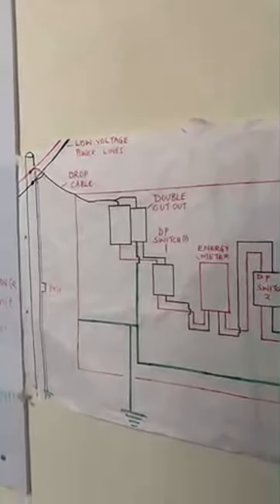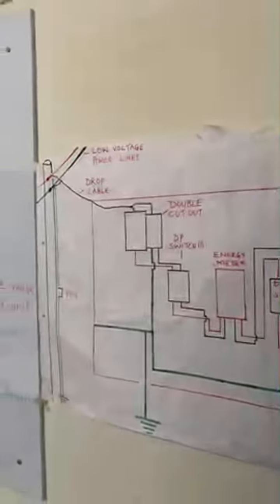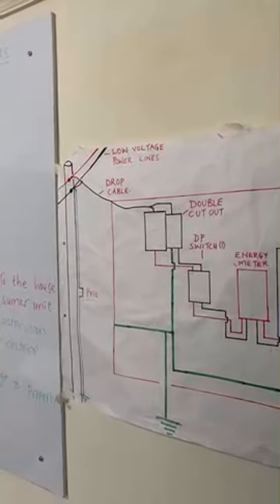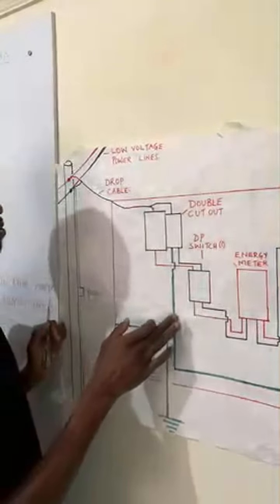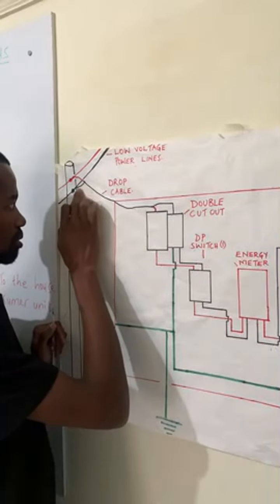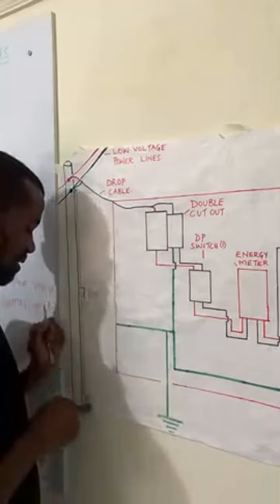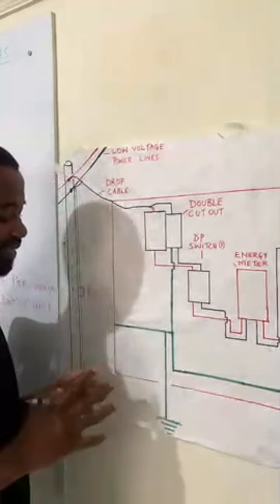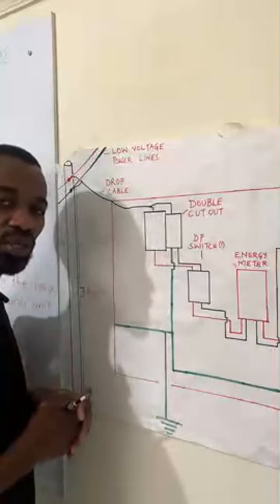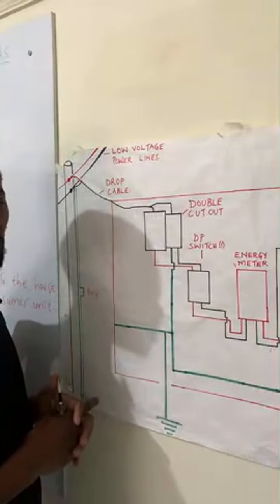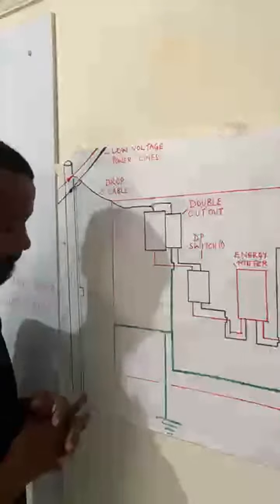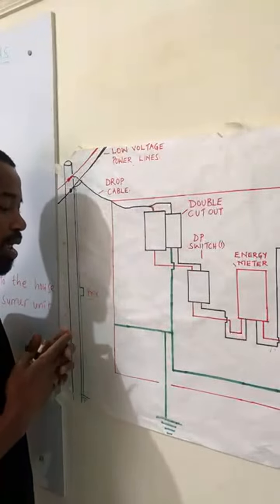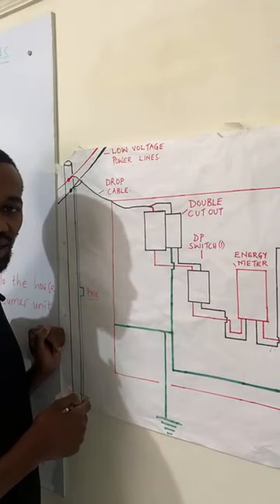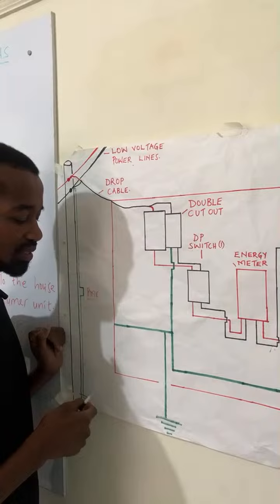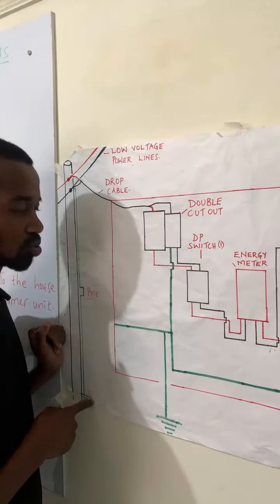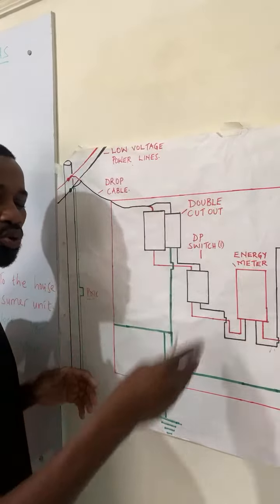Now, because we have talked about that particular bond, one thing that you need to know is that in case your earth connection is broken, but you have a good PME, then these charges will flow back through the neutral connection to this pole that is here, and down to the PME, to the earth. Now, it does not just go to the earth, it goes back to the transformer, the source. Big question here is how? Do you have another wire down there? Do you have another conductor down there? The earth itself conducts, of course, with a very big resistance, but these charges will definitely find their way to the source.